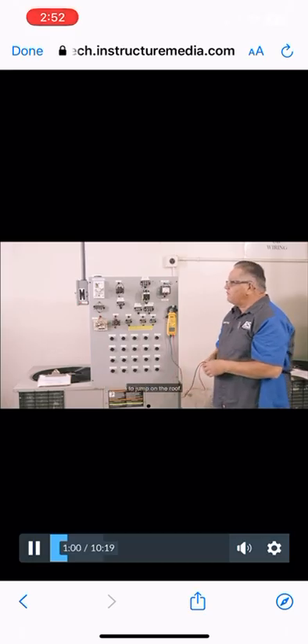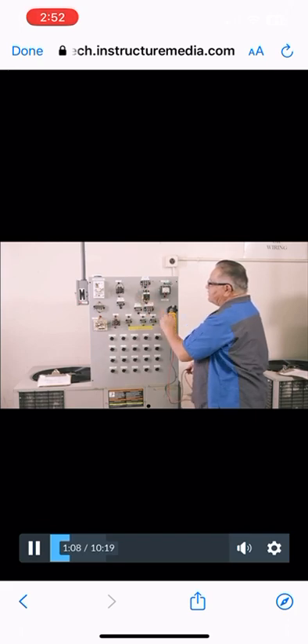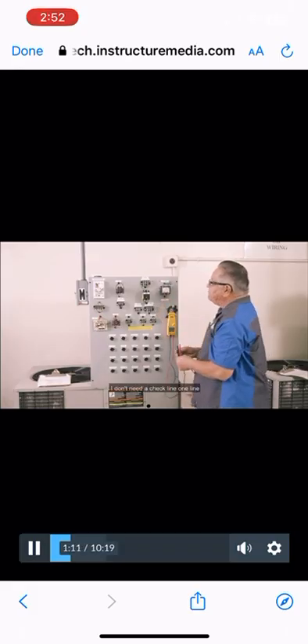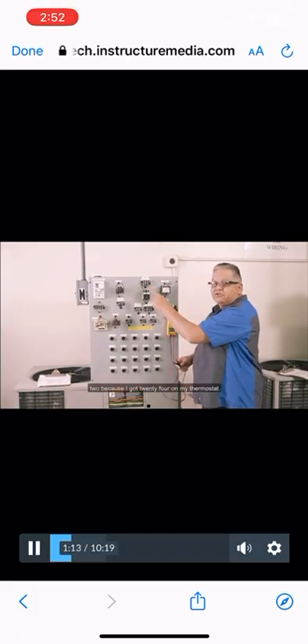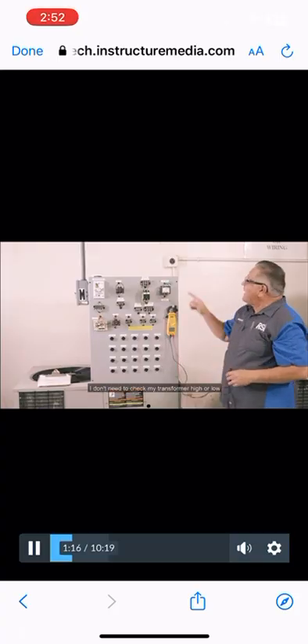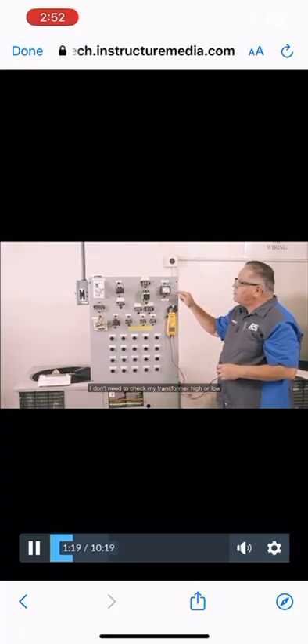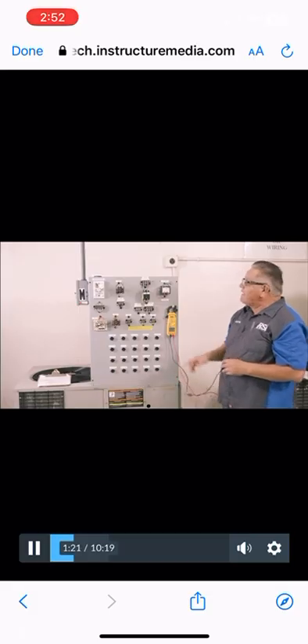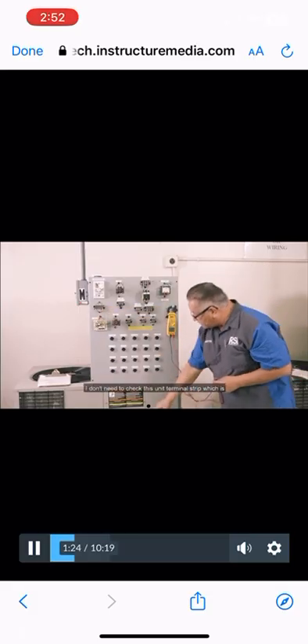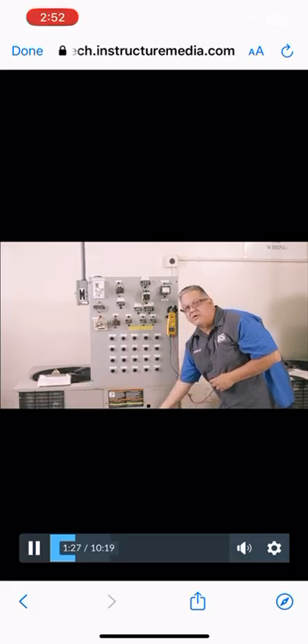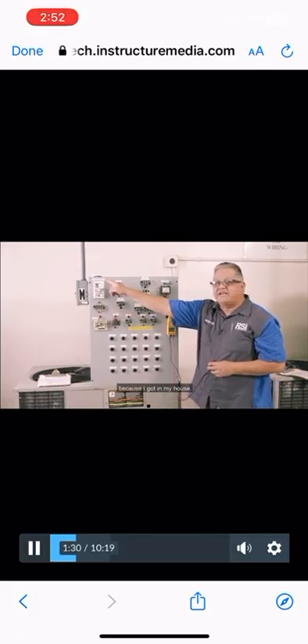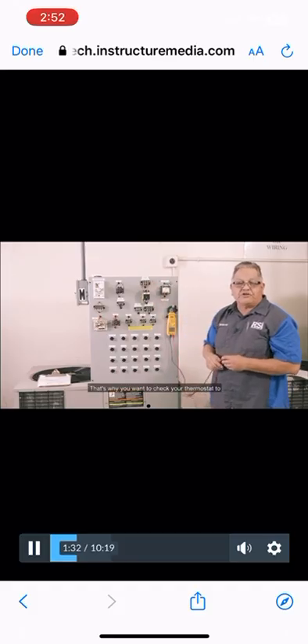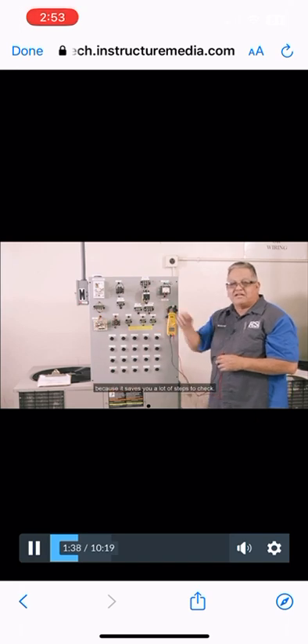I'm going to jump on the roof. First thing I need to do, I got 24 on the thermostat, so I'm going to jump on the roof. I don't need to check line 1, line 2, because I got 24 on my thermostat. I don't need to check my transformer, high or low. I don't need to check this unit terminal strip, which is on the other side of this little hole where your thermostat wire goes in, because I know there's 24 there because I got it in my house. That's why you want to check your thermostat to see if you got voltage before you jump on the roof, because it saves you a lot of steps to check.